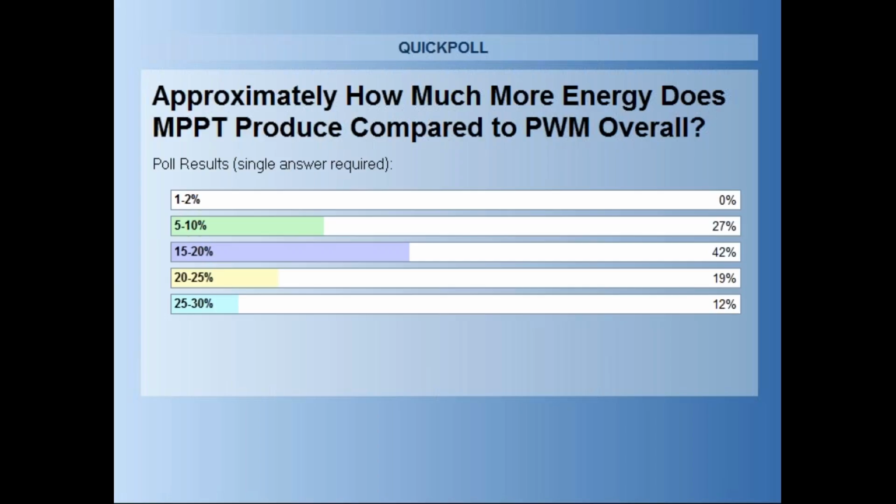Now, for a maximum power point tracking unit, it's different because, again, you are sizing based upon wattage. So there you can do all kinds of things. Most of those are rated anywhere between 80 volts maximum to 150, depending upon the unit you have. Most of those manufacturers are going to have some type of sizing chart on their website to help you with that. But you want to be very careful. If you exceed that voltage on most of these units, there is overcurrent protection inside them, transorbs, resistors, things like that, that will pretty much melt down and the unit will become unusable at that point.